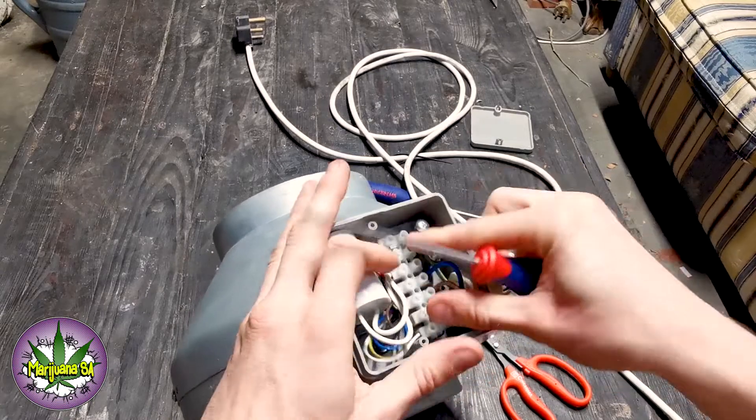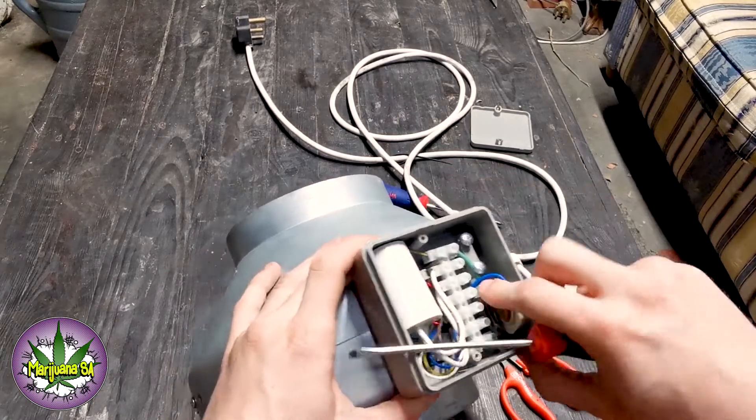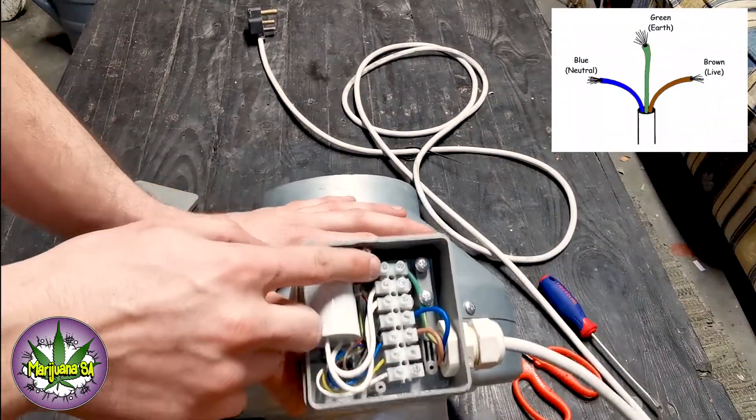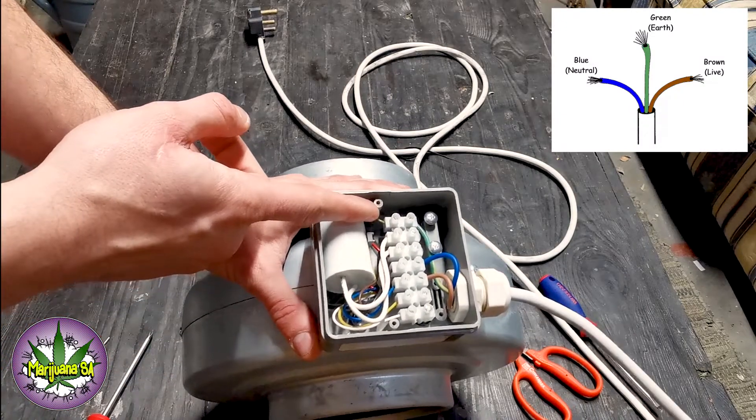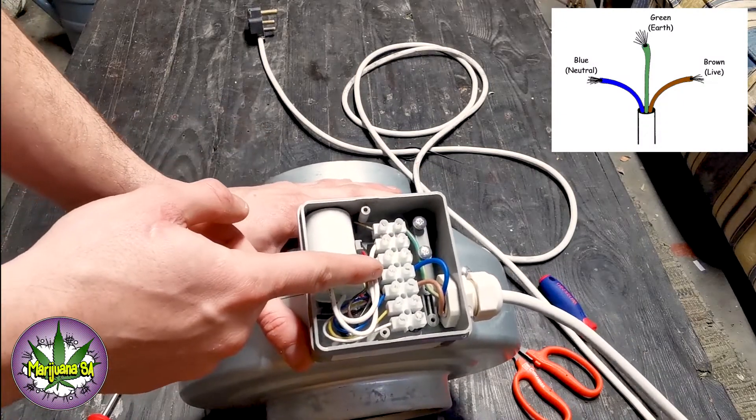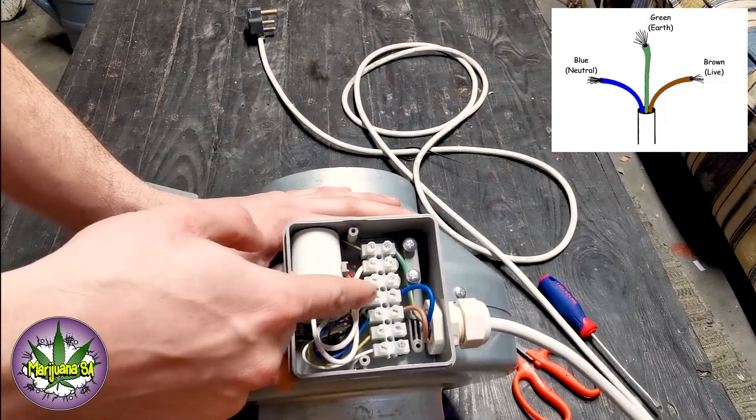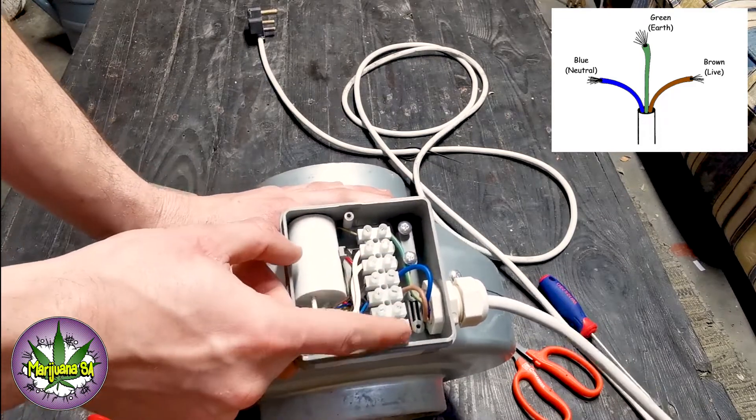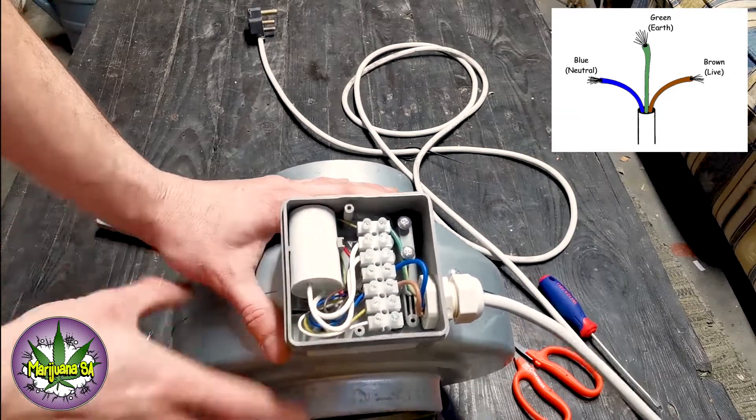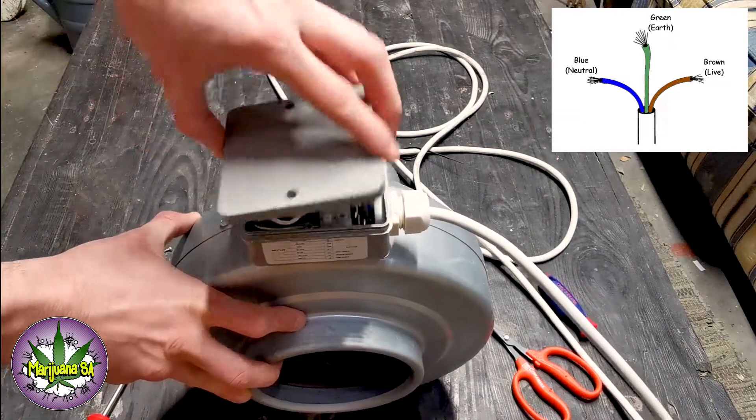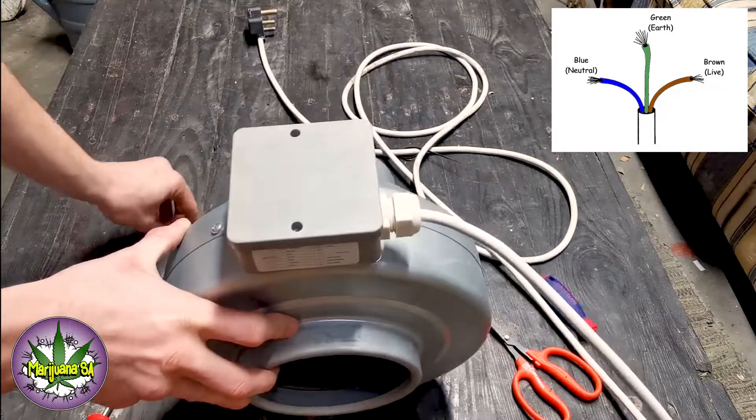So in closing we wired our yellow to the top, this is our earth, the blue which is our neutral to the black wire, and then we selected our speed. I went for the fastest speed and wired my live here and then closed the unit back up again as opened, ready for action. Thanks for watching guys, I hope you enjoyed the video. If you did please like and subscribe and till next time, peace out.